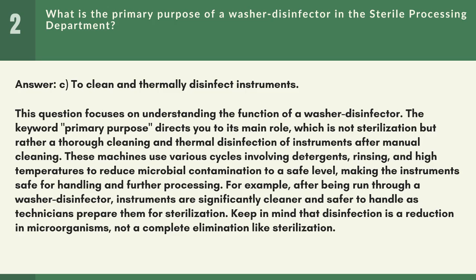This question focuses on understanding the function of a washer disinfector. The keyword primary purpose directs you to its main role, which is not sterilization but rather a thorough cleaning and thermal disinfection of instruments after manual cleaning. These machines use various cycles involving detergents, rinsing, and high temperatures to reduce microbial contamination to a safe level, making the instruments safe for handling and further processing.